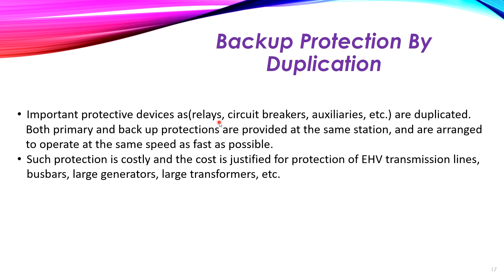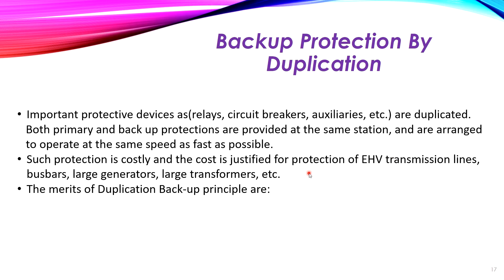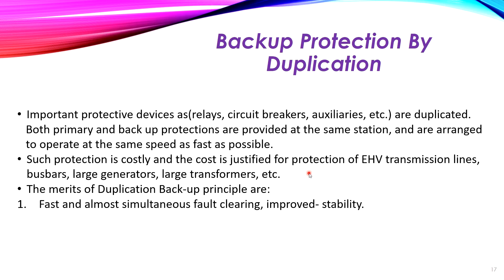This type is used for very important components such as extra high voltage transmission lines, large generators, bus bars, and large transformers. The merit of the duplication backup principle is number one: it is fast and almost simultaneous fault clearing, which improves stability of the power system. Number two: complete reliability can be assured because all protection components are duplicated. The disadvantage is of course the large cost of this system.